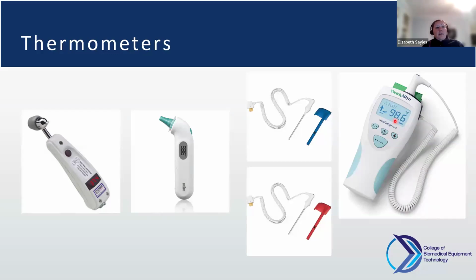Failures of these Welch Allyn thermometers usually end up being bad probes. The lot date on these probes tells you how old they are, because it's a specific date. And if you call Welch Allyn and they're within 1 year, they'll send you a replacement for free based on the lot number, which is really nice. I like how they did that with the manufacturing process. When the probe fails, I believe it's an E05 error code, and those come up pretty frequently in the calls you'll get for these types of devices. The batteries are user replaceable. They're AA batteries. So there's not really too much aside from verifying the functionality of the thermometer with that calibration key to make sure it's working as it should.